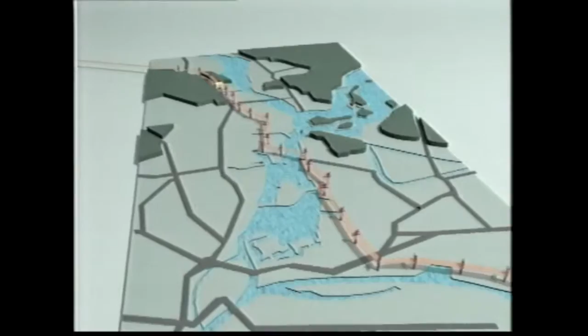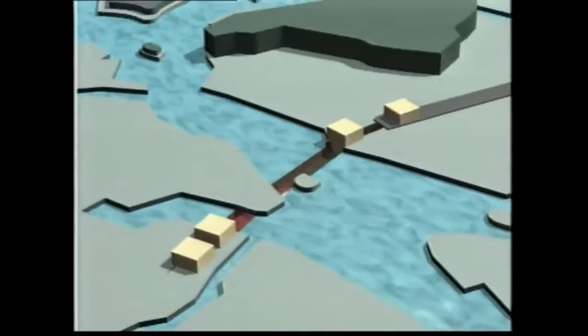To connect the two power supply systems, an interlink is planned by the Bewag. The 380 kilovolt overhead line from Helmstedt to Berlin is to be extended from the city boundary at Spandau to the Reuter transformer station. Contrary to these plans, however, the connection has to be laid underground from the new switching station at Teufelsbruck on.